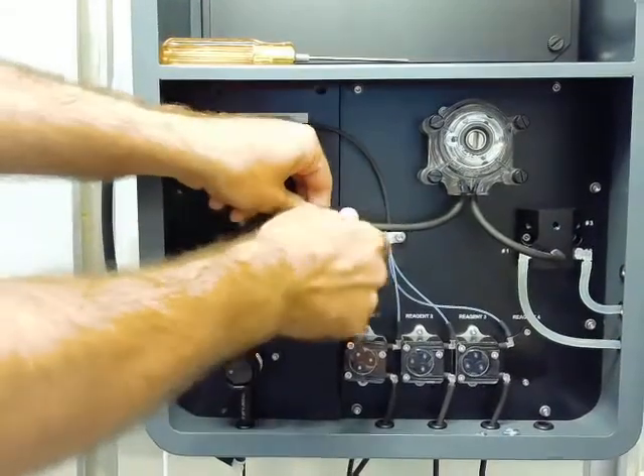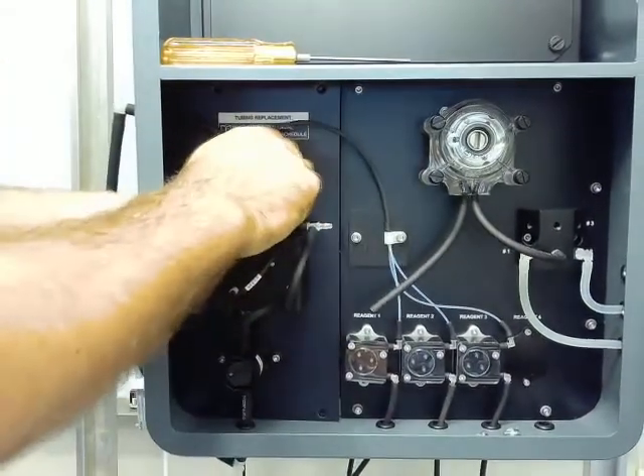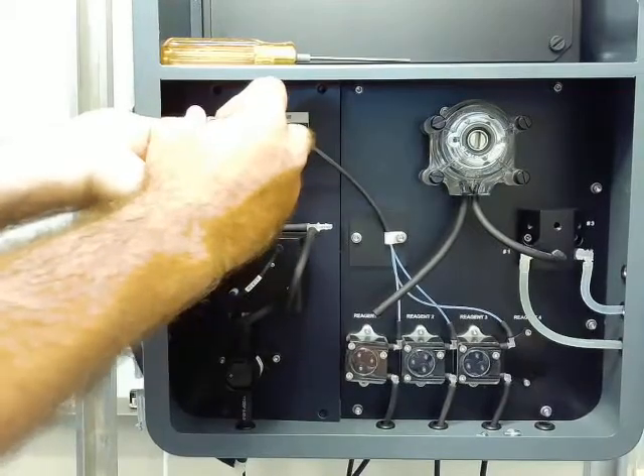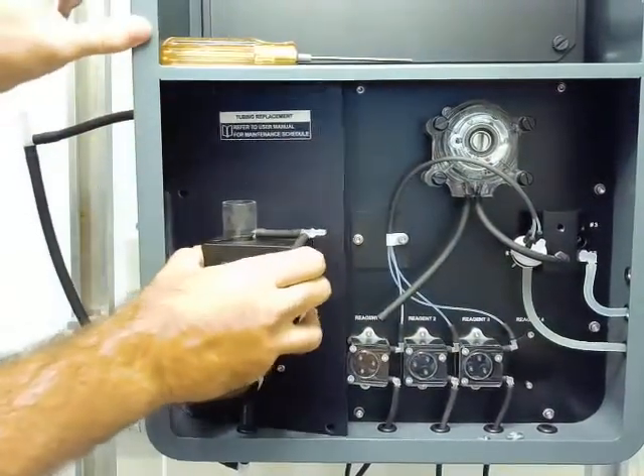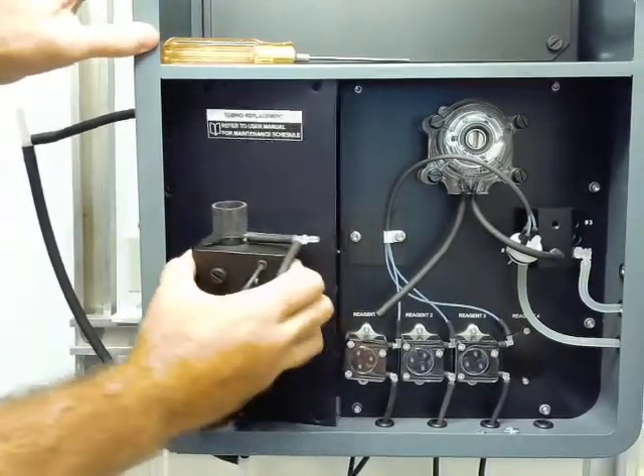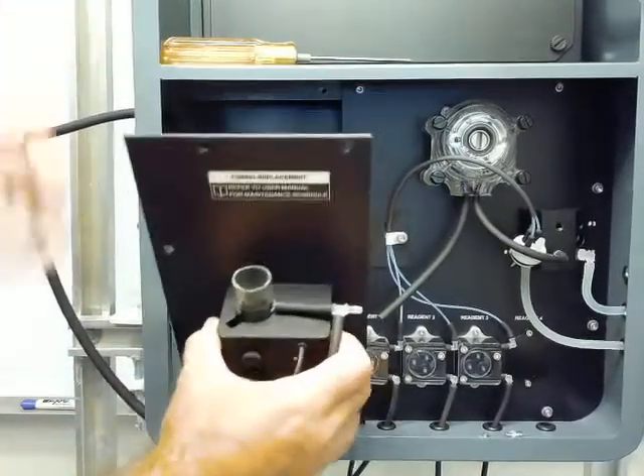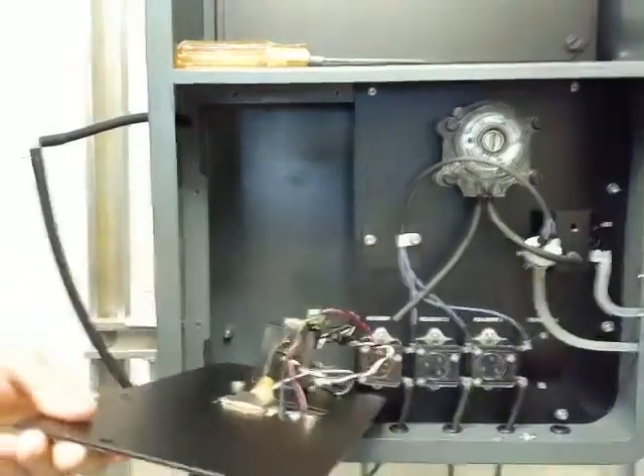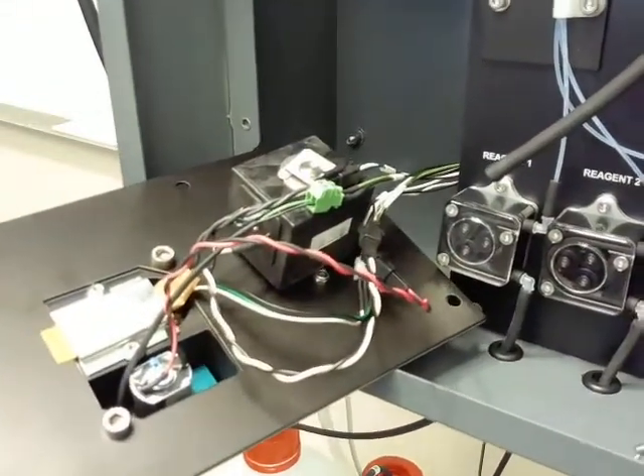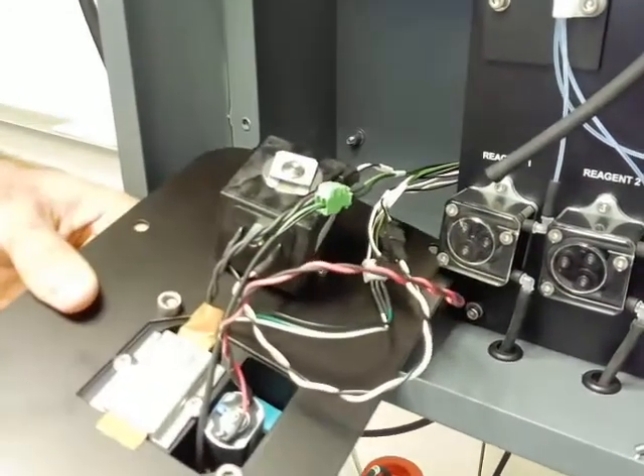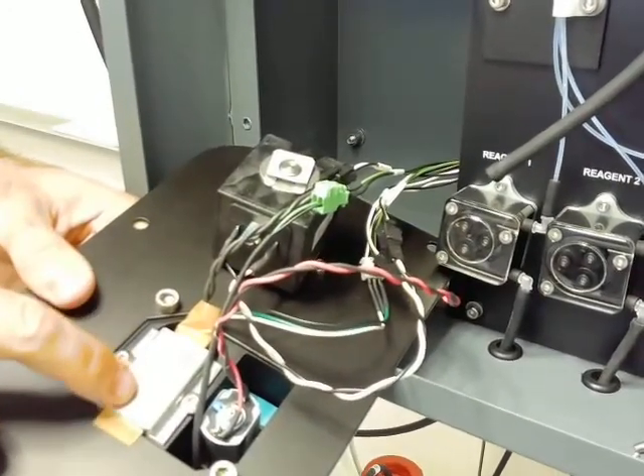So now with the panel loose, we'll just have to disconnect this tube here, pull out our flow cell cap, and loosen the vent tubing so we can free up that space. Just slide this forward and out. So what we can see now is what's behind our flow cell block. Here we can see this little metal piece is our heater.